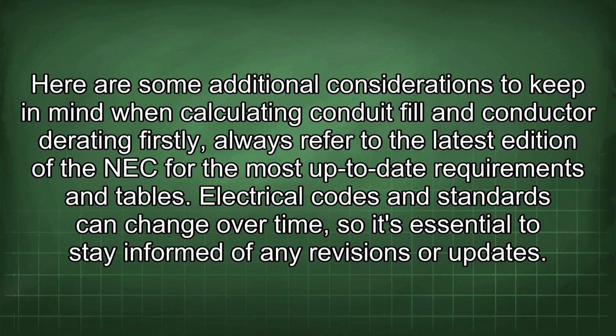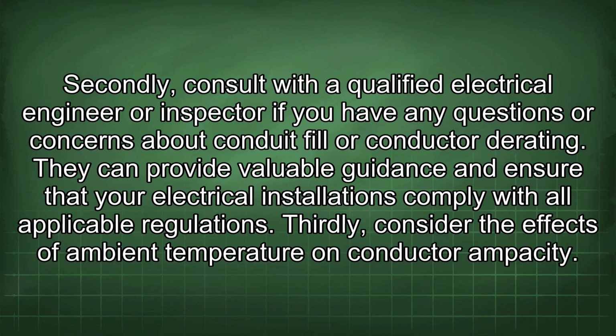Here are some additional considerations to keep in mind when calculating conduit fill and conductor derating. Firstly, always refer to the latest edition of the NEC for the most up-to-date requirements and tables. Electrical codes and standards can change over time, so it's essential to stay informed of any revisions or updates. Secondly, consult with a qualified electrical engineer or inspector if you have any questions or concerns about conduit fill or conductor derating. They can provide valuable guidance and ensure that your electrical installations comply with all applicable regulations.